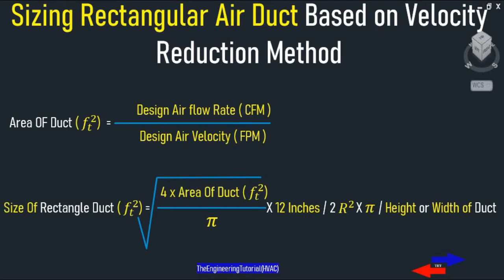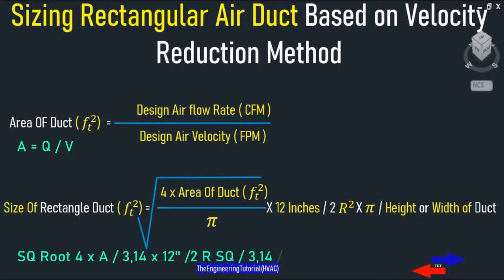To find all these branch and main duct sizes we use the formula: airflow rate divided by air velocity, then take the square root of 4 times the area divided by pi, times 12 inches divided by 2 R squared times pi, divided by the height or width of the air duct.